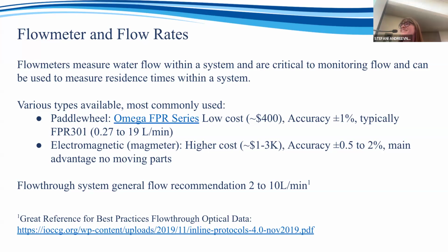Yes, something you want to say? Well, I despise the paddle wheels, but maybe it depends on how much eelgrass there is where you live. I think they're around originally because they were a lot cheaper. I think we've seen setups that are probably a lot less than that. I think the electromagnetic stuff and other variations on that are coming down a lot in price. I keep looking at it and I think we may be at the point where we could just switch to nice things that didn't have anything in the flow stream, but I don't have a recommendation.